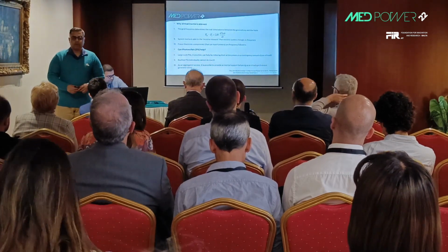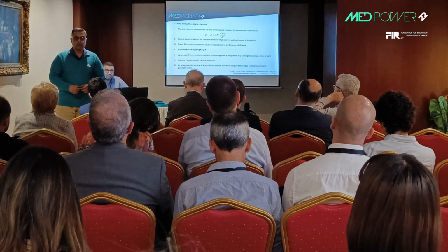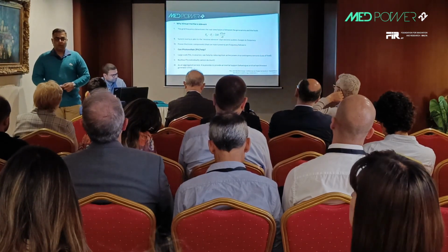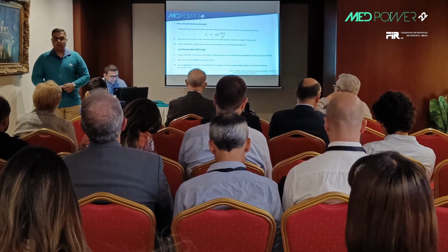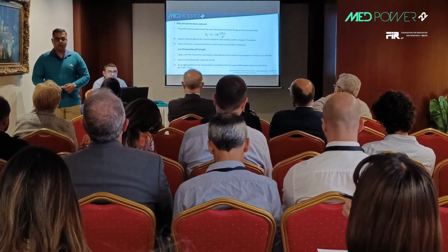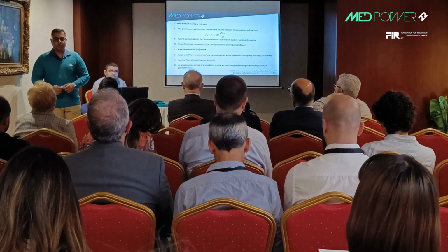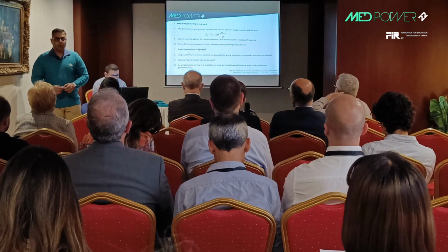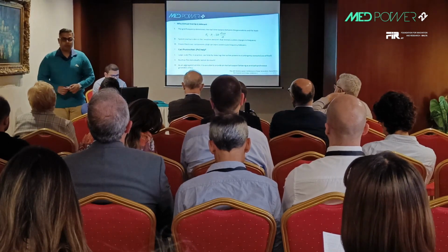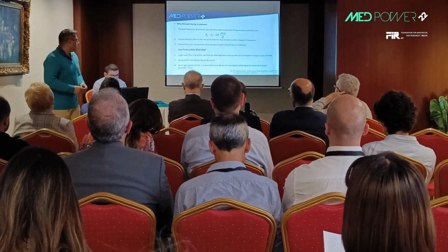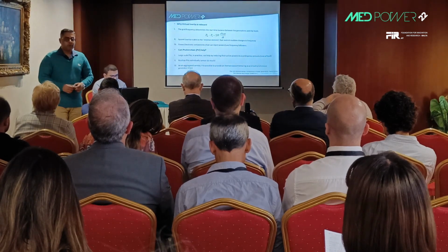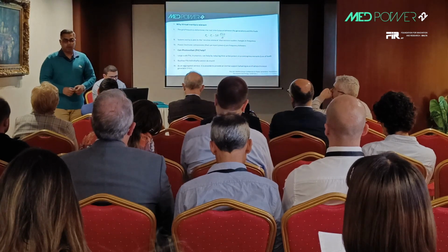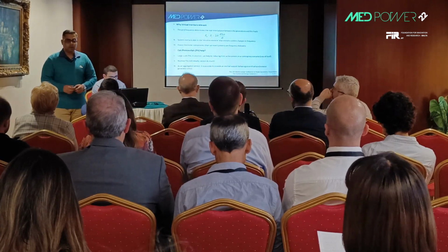Power electronic components such as photovoltaics and wind are inverter-based sources, so they cannot generate their own frequency. They are frequency followers, so they are negative loads. Negative load means they are not helping in providing the system inertia at all. But do photovoltaics help? They do help generally, especially in a large scale farm.